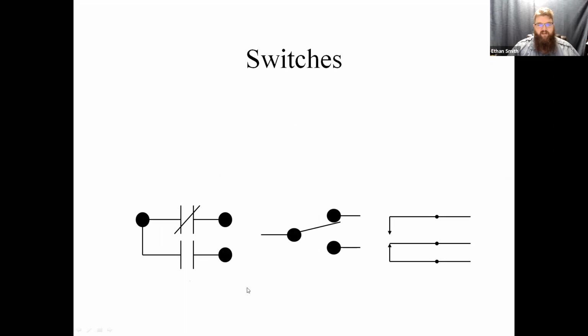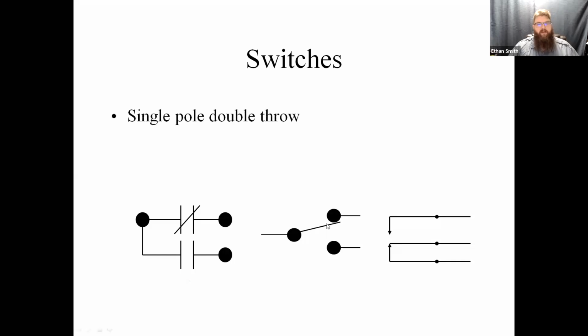Okay, so I'm going to throw this one out here, guys. What do you think this is? Single pole, double throw. This is a single pole double throw. So we've got that normally closed position up here, normally open down here, normally closed up here, normally open down here, and the same thing down here. It's just flipped over. It's got one normally closed and one normally open on a single pole double throw. Okay, we can keep going here. What's this one, guys? Double pole, double throw.